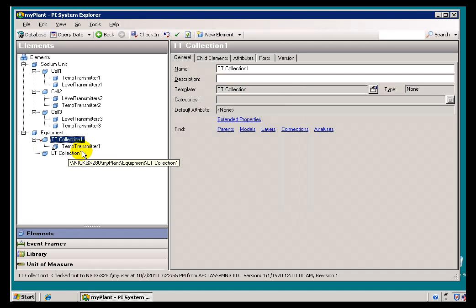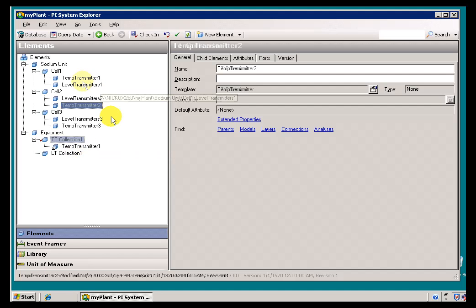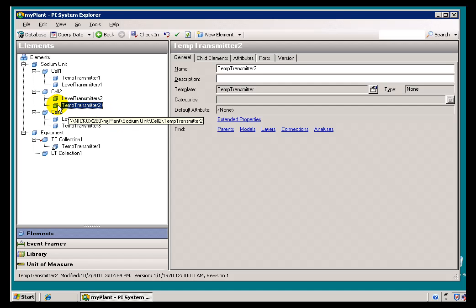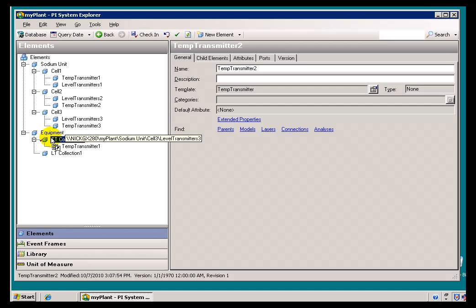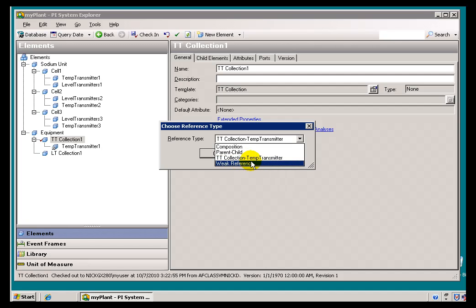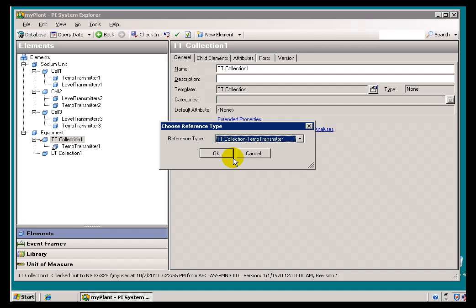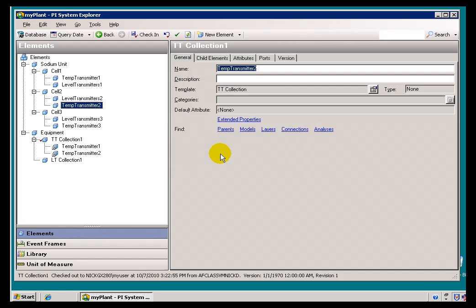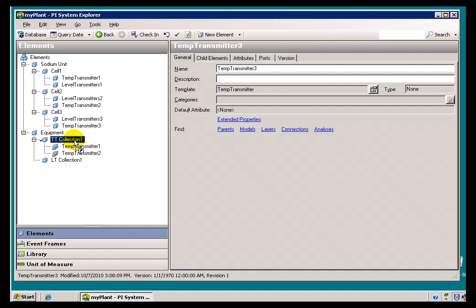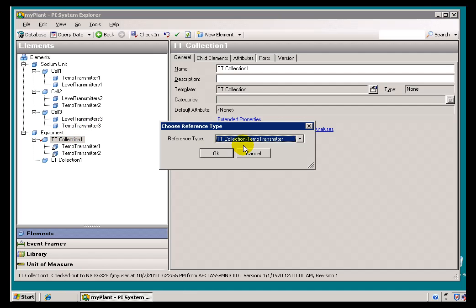Now we have a Reference to there, but it's a weak Reference Type — the one I defined. I could also have done that by drag and drop. I can grab this Temperature Transmitter and just drag and drop; it has the effect of adding a Reference. When I do this, it detects that we're trying to add a Reference and shows me just those Reference Types that are available. Again, we're going to choose the one we've defined. I'll do the same for this one — dragging and dropping does the same thing as Add an Element Reference, using that Reference Type we want.